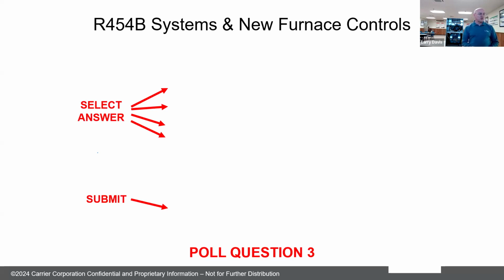When is a single evacuation during the recovery process not sufficient? It is not sufficient when you're recovering 454B from an existing system. Any other time, if you're installing a new one that's never had refrigerant in it, you're fine for single evacuation. If you're recovering 410A and putting in a 454B, single evacuation's fine. And then the bottom one is not correct. So the correct answer was the top one. If you're pulling out 454B refrigerant, you're recovering that. You cannot do just a single recovery process. You have to do multiple recovery, and we'll talk about that. So my mistake on the presentation there. I've got to fix that for next week.